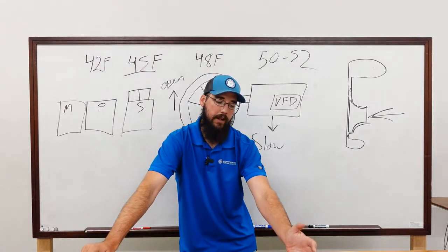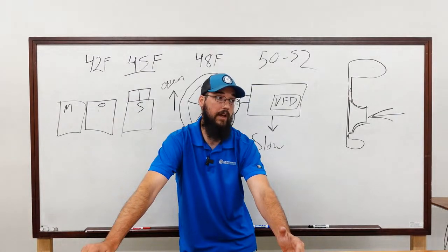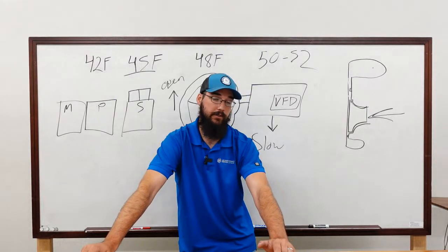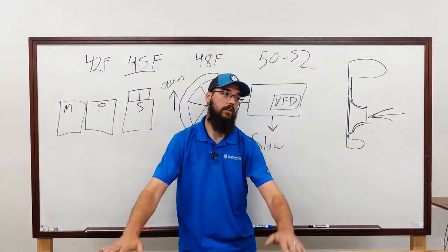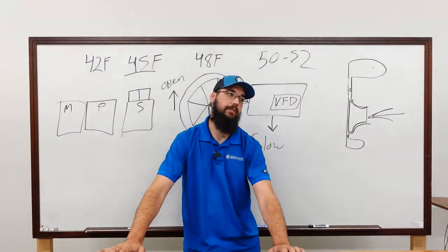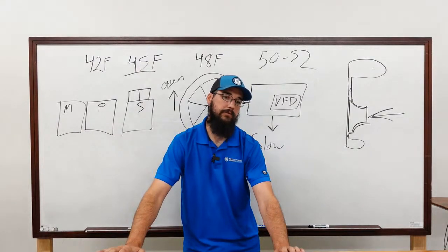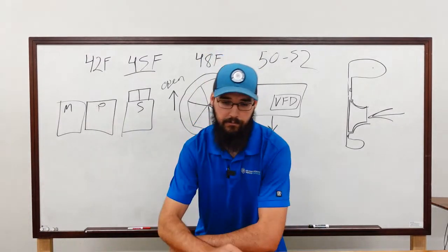Because you've got to think about it, as those IGVs pinch down, the suction pressure you're reading on the evaporator is not the actual pressure coming into the inlet of the nose, because it's restricted down. So you're actually technically pulling the pressure coming into the inlet of the nose lower than your evaporator pressure is, because the vanes are closed far enough. So that will push you into kind of a stall state without having a high lift that is readable from the display or anywhere else. Anyway, we're not going to sit on that too much, because that could get kind of confusing.